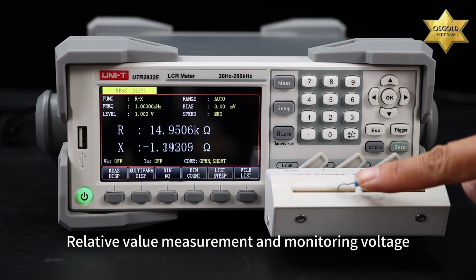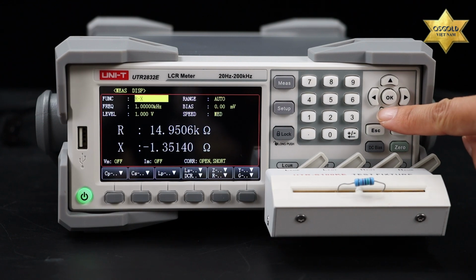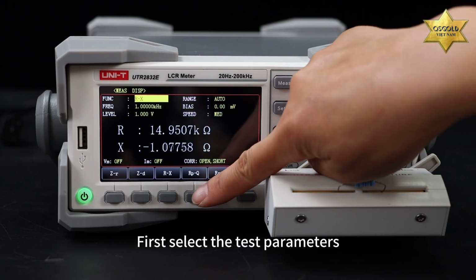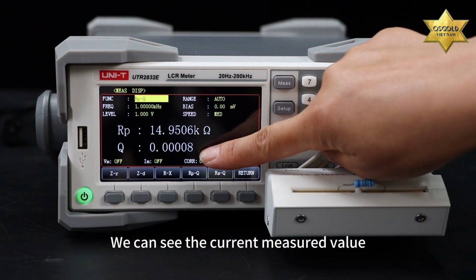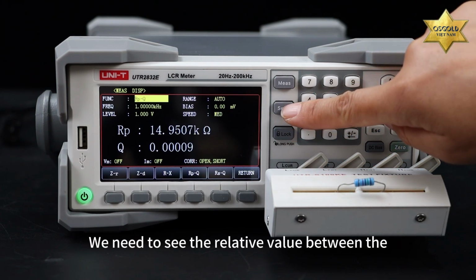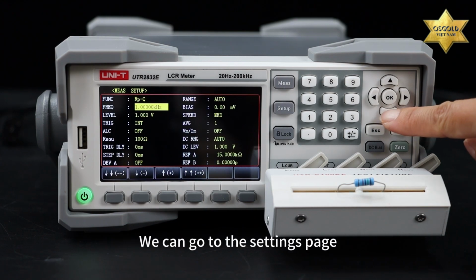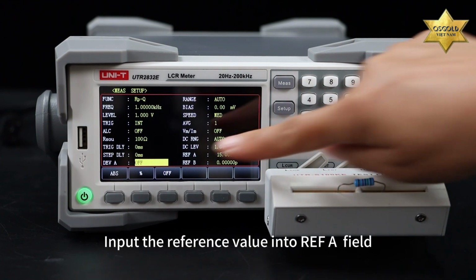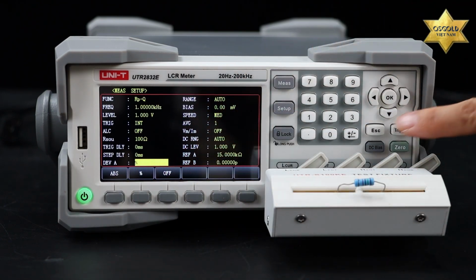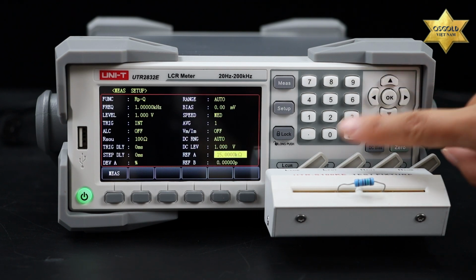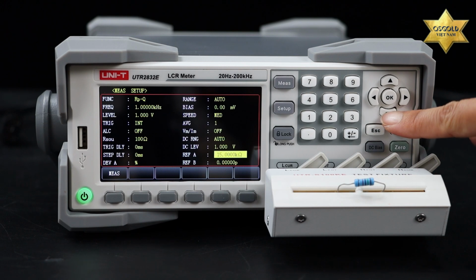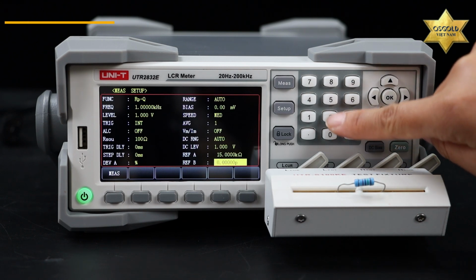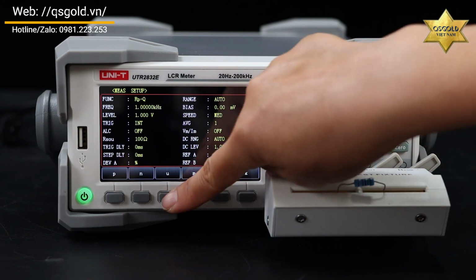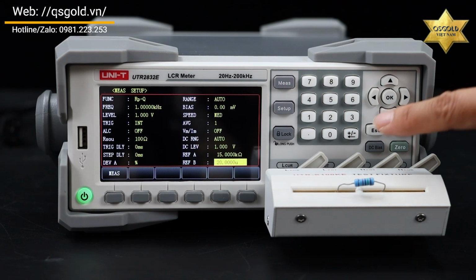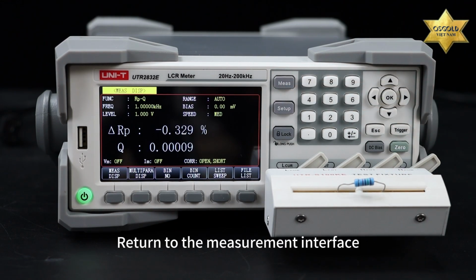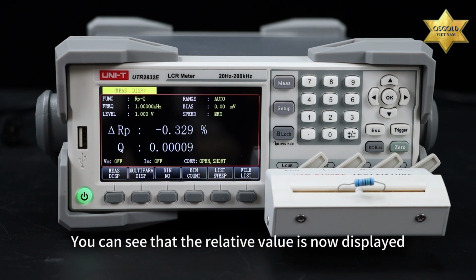Let's take a look at relative value measurement and monitoring voltage. First, select the test parameters. We can see the current measured value. In some scenarios, we need to see the relative value between the current measurement and the standard value. We can go to the settings page, turn on Dev A, input the reference value into Ref A field. Return to the measurement interface.